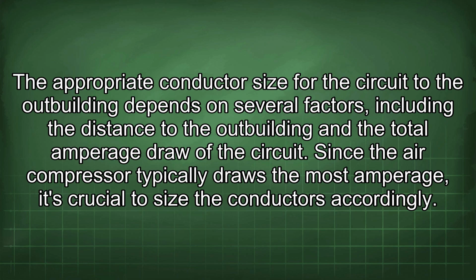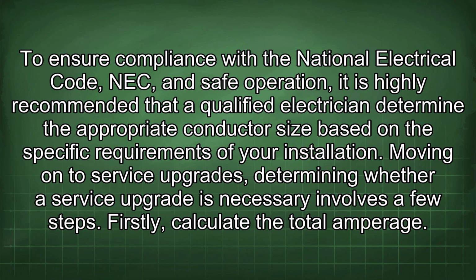The appropriate conductor size for the circuit to the outbuilding depends on several factors, including the distance to the outbuilding and the total amperage draw of the circuit. Since the air compressor typically draws the most amperage, it's crucial to size the conductors accordingly. To ensure compliance with the National Electrical Code (NEC) and safe operation, it is highly recommended that a qualified electrician determine the appropriate conductor size based on the specific requirements of your installation.